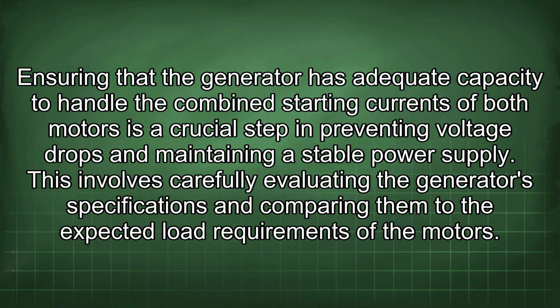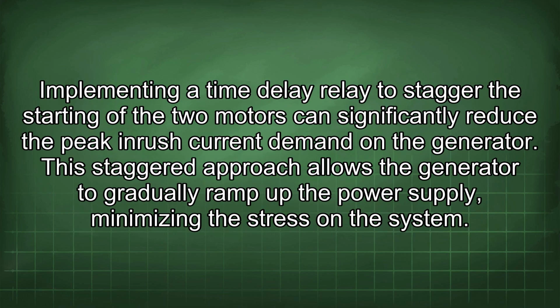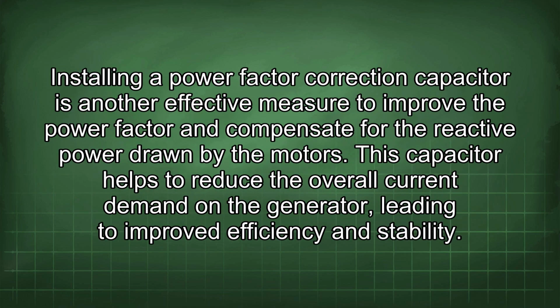This involves carefully evaluating the generator's specifications and comparing them to the expected load requirements of the motors. Implementing a time delay relay to stagger the starting of the two motors can significantly reduce the peak inrush current demand on the generator. This staggered approach allows the generator to gradually ramp up the power supply, minimizing the stress on the system. Installing a power factor correction capacitor is another effective measure to improve the power factor and compensate for the reactive power drawn by the motors. This capacitor helps to reduce the overall current demand on the generator, leading to improved efficiency and stability.